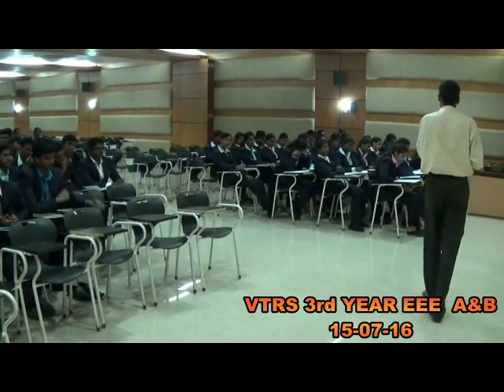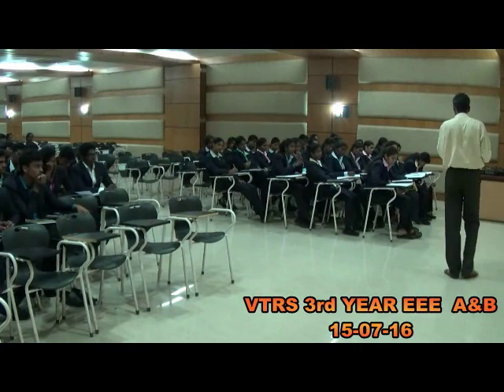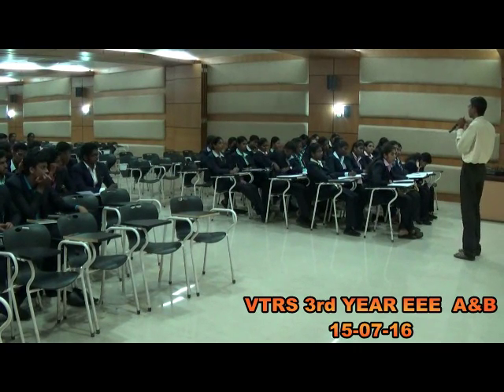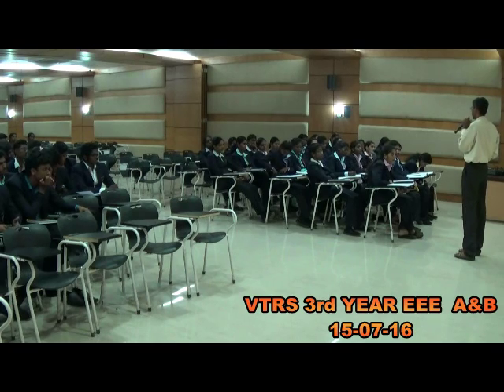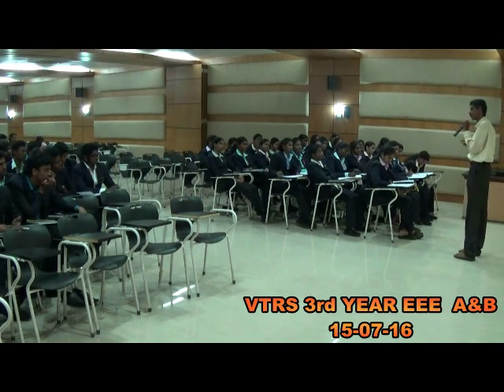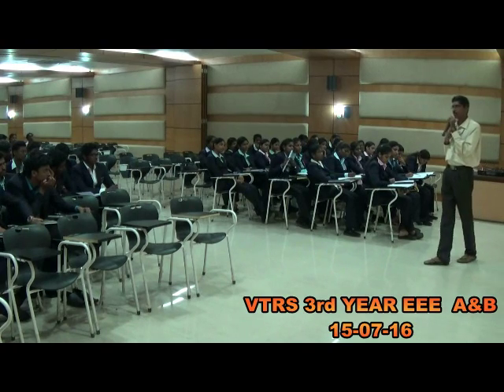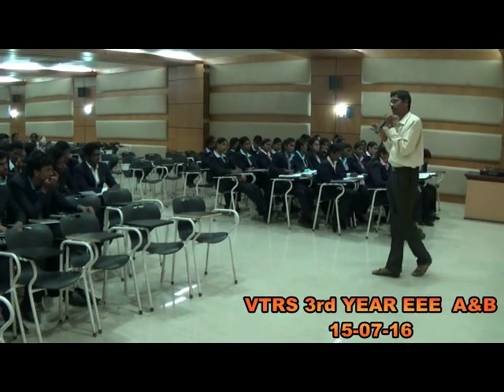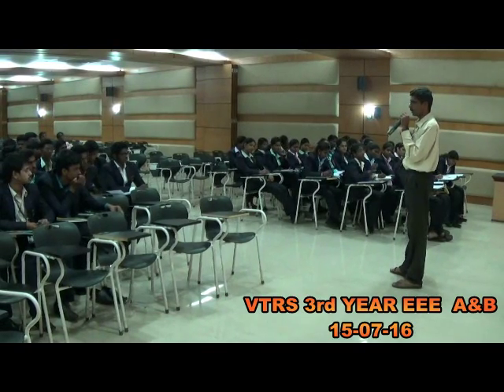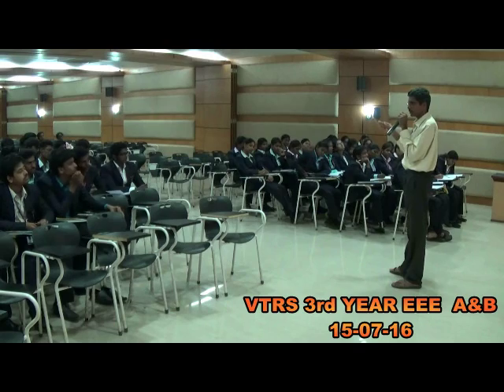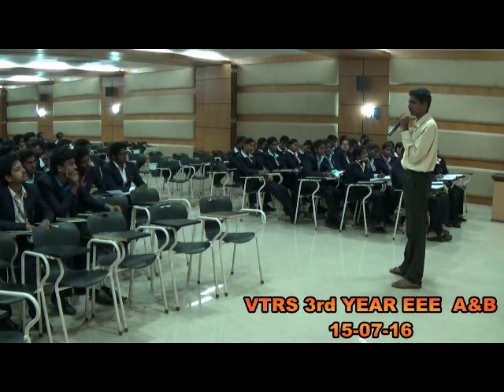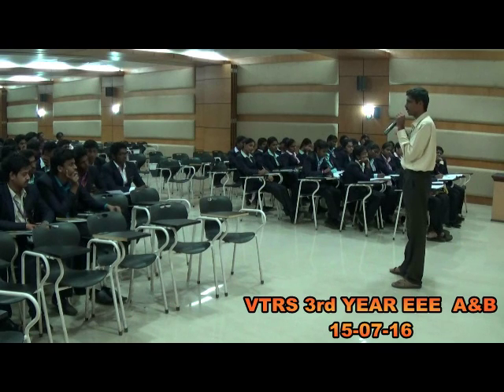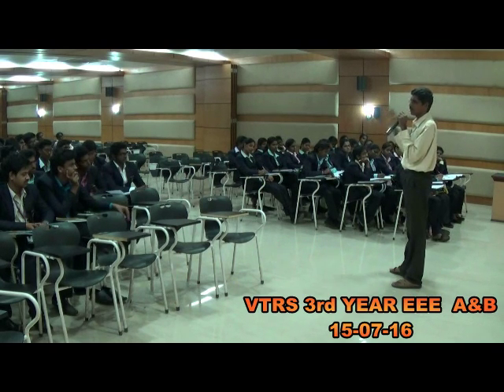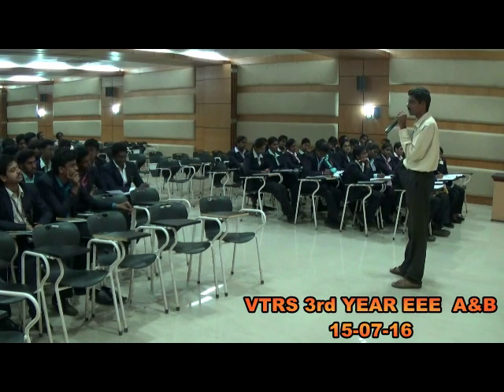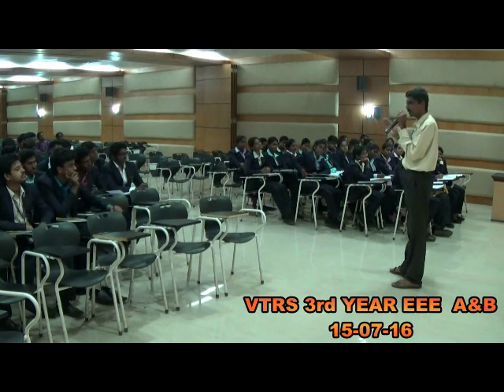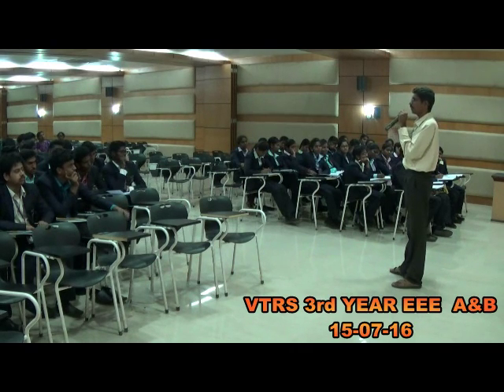One of the most important interview questions, wherever you go for a power system, is: what is the significance of short circuit capacity? It has different names: fault level, short circuit capacity, short circuit MVA; all are the same. If the short circuit capacity is greater than 10 per unit, then it is a strong system. If it is less than 10 per unit, then it is a weak system.